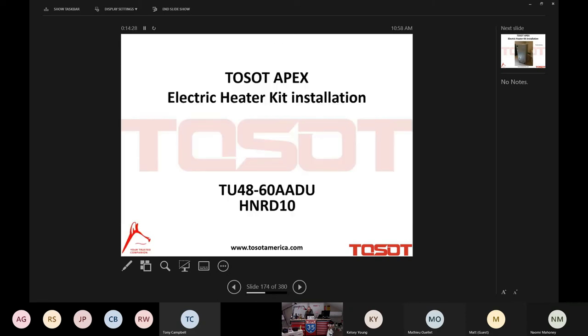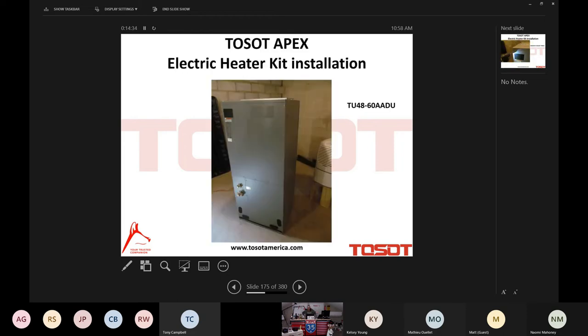Really, really nice stuff. Okay, let's take a look at the electric heater kit. And again, there are four of them: 8 kW, 10, 15, and 20. A good idea, not necessary, but a good idea, is to install it before installing the fan coil. It can be retrofitted after the fact. I'll show you that in just a moment. But in the cases where you know you're going to need this, and I've got to believe every one of your applications in Canada would call for electric backup, just based upon what I know of your climate there. Here in Pennsylvania, where I don't encounter anything like you guys do, I took advantage of it here.